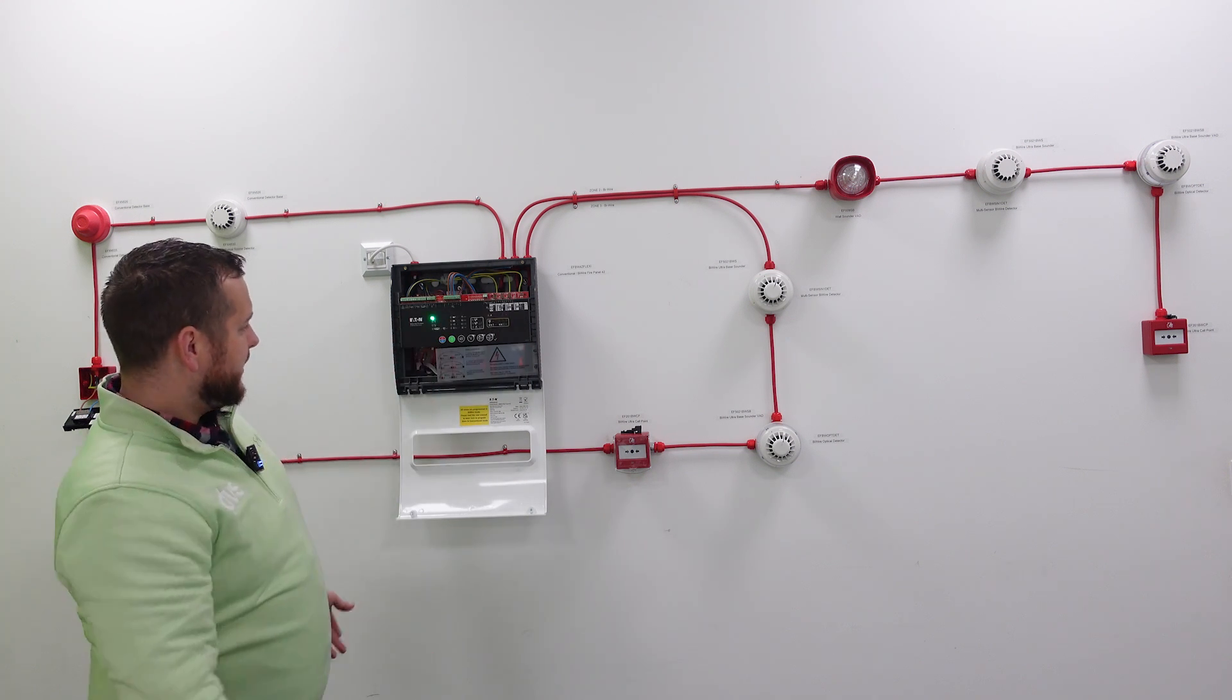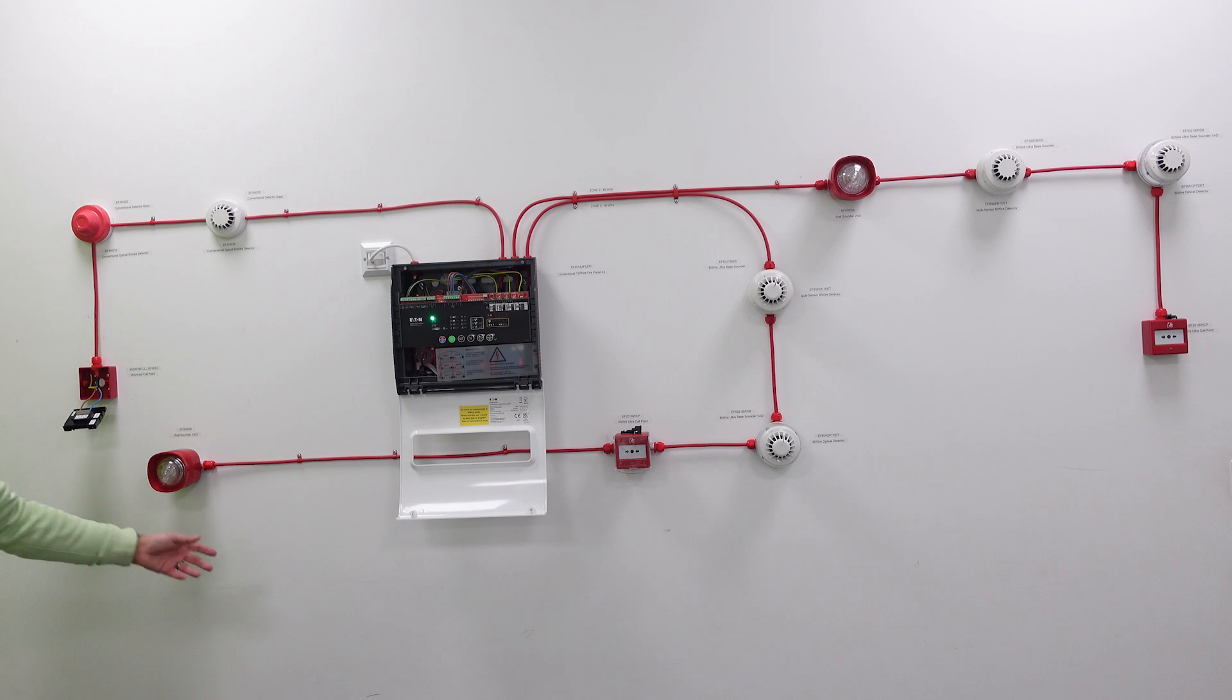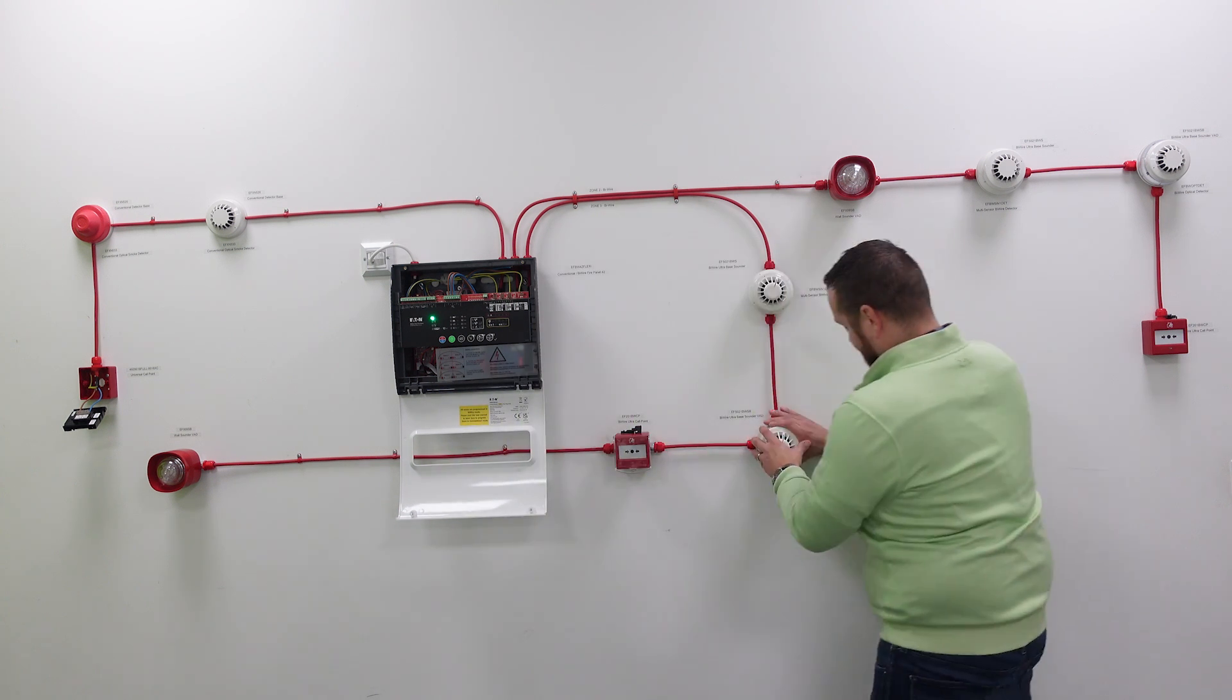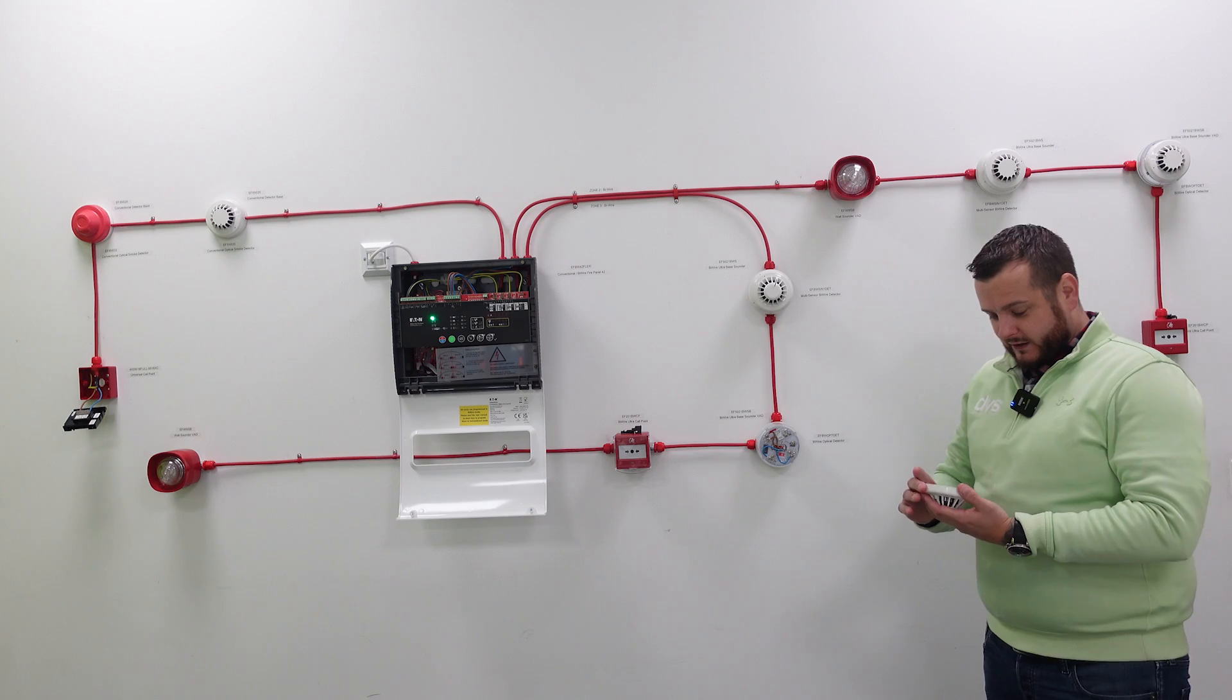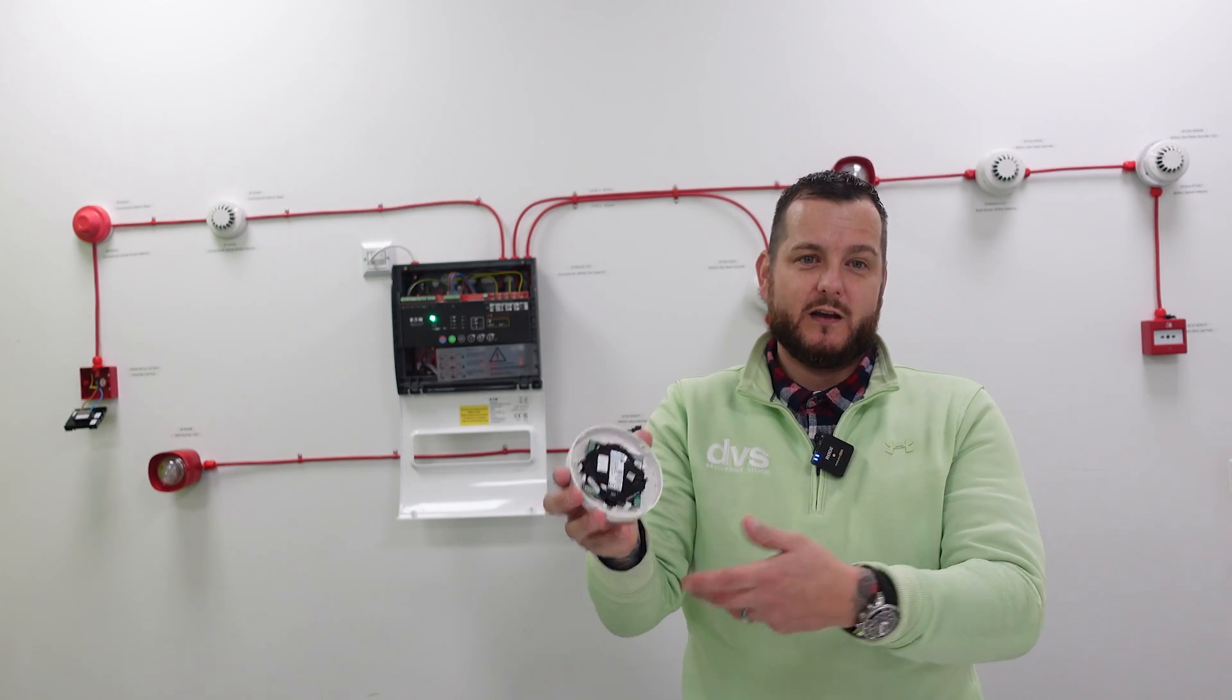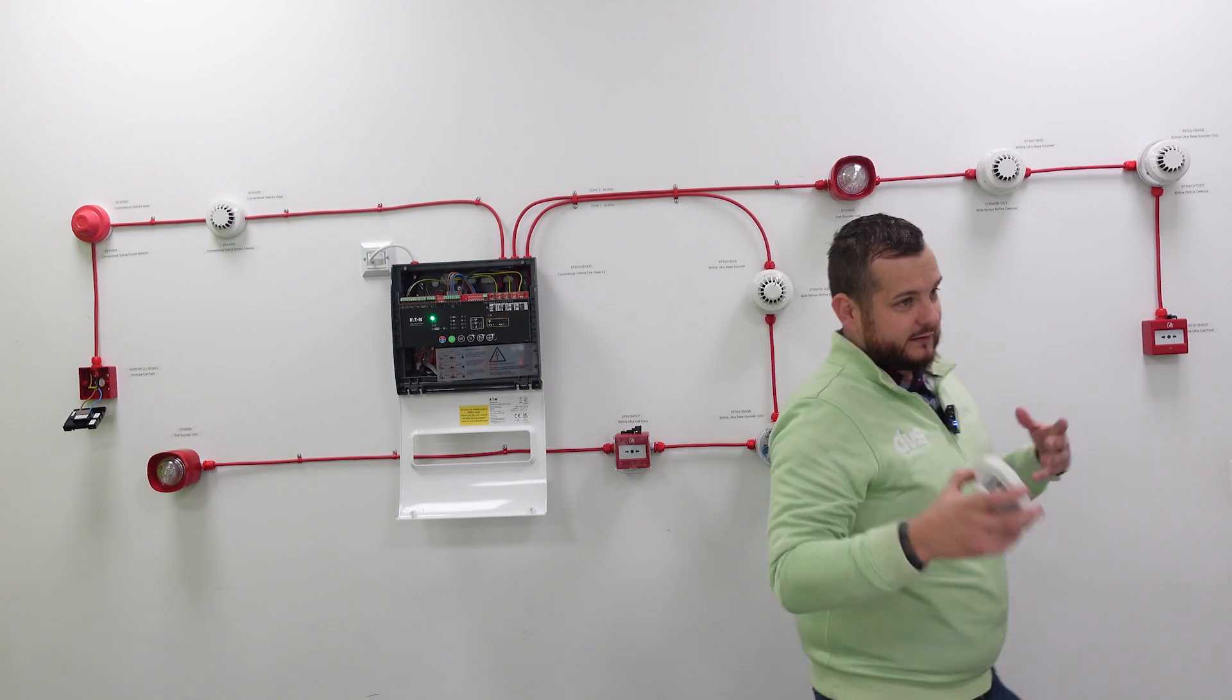It has two on-board sounder circuits. Again, you just fit the appropriate end-of-line module, end-of-line resistor, etc., depending if it's ByWire or conventional. But focusing on the ByWire, we come out, we've got our detection circuits, call points, and then another VAD here, and that will be fitted as per the design. Very good quality. You can twist these off the bases. We've got a VAD sounder base here. Cables come in and you can see here these are replaceable heads.